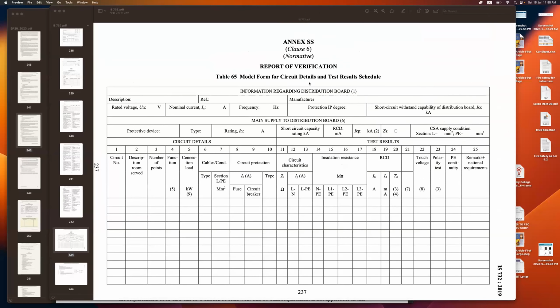Yes. So it's a model form for circuit details and test result schedule. It's as per IEC 60364. This is in IS 732. The same thing is also available in NEC. So they're asking you for the rating of the circuit breaker, the type, then the maximum loop impedance that would cause instantaneous tripping, the short circuit currents between line and neutral, line and protective earth, then insulation resistance between neutral and protective earth, line 1 and protective earth, line 2 protective earth, line 3 protective earth, RCD tripping current value, how many milliamps it trips at, how much time it takes to trip, touch voltage, polarity, protective conductor continuity, and so on and so forth.